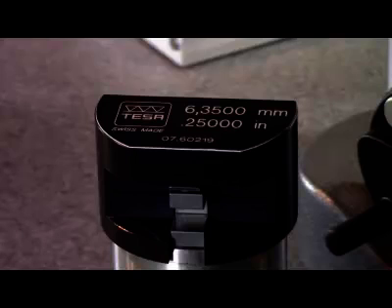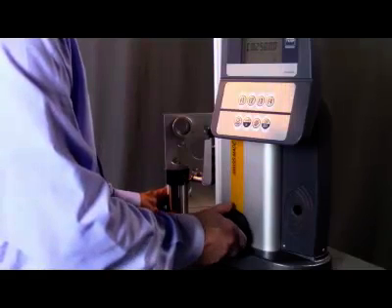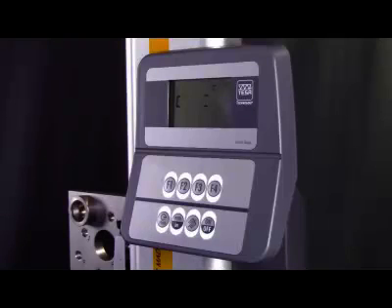In this case, the display reads 0.25000 and the setting master is also 0.25000. It doesn't matter if you start by making contact on the top or the bottom, but you will take four hits with the probe on the setting master. When you're finished, the display reads start two and the gauge is ready to measure.